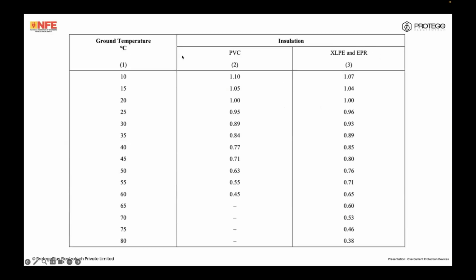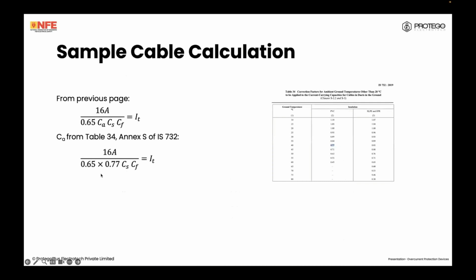Now, the ambient temperature of the ground is 40 degrees Celsius. See, the important thing when it comes to cables is that we need to find out what the maximum operating temperature the cable can operate at, which is dependent on the insulation. However, just because the cable insulation can withstand, say, 90 degrees in XLPE, does not mean that the connected equipment, the terminals of the MCCBs, terminal blocks, and so on and so forth, can also withstand this value. So, unless we have information that specifically tells us that the terminals and connected equipment can withstand 90 degrees, we have to assume 70 degrees. So, use the PVC factor even for an XLPE cable. So this is 0.77. So plug that in right there.